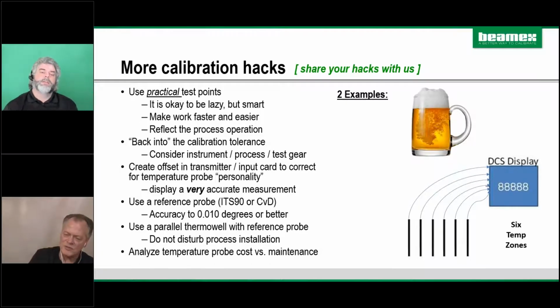If they adjusted zone 1 to go up in temperature to match zone 6, they knew they were in sync. It actually increased their quality and throughput by using a dry block and doing this offset. So these are real deals.